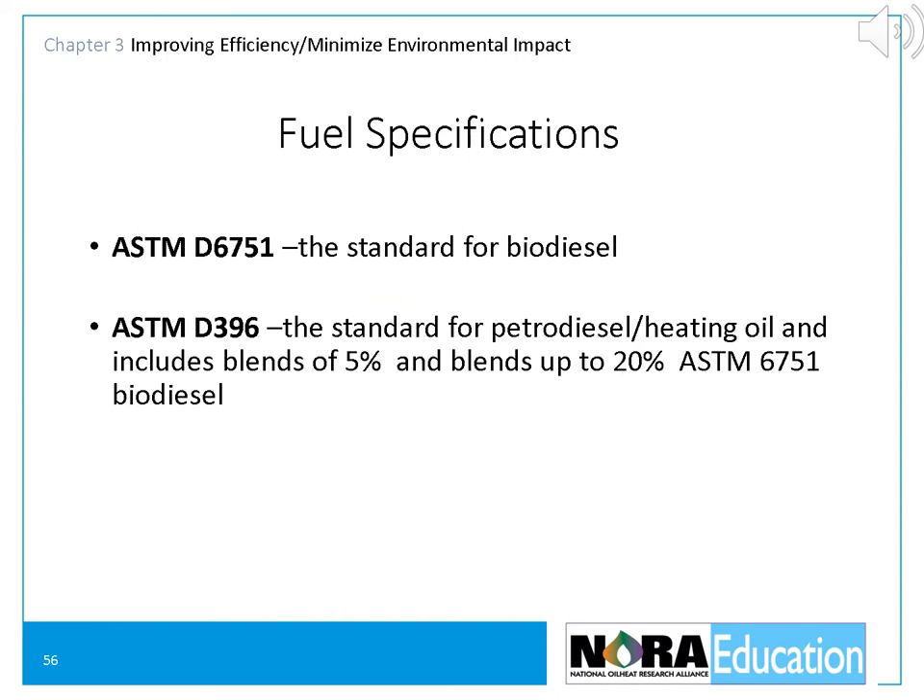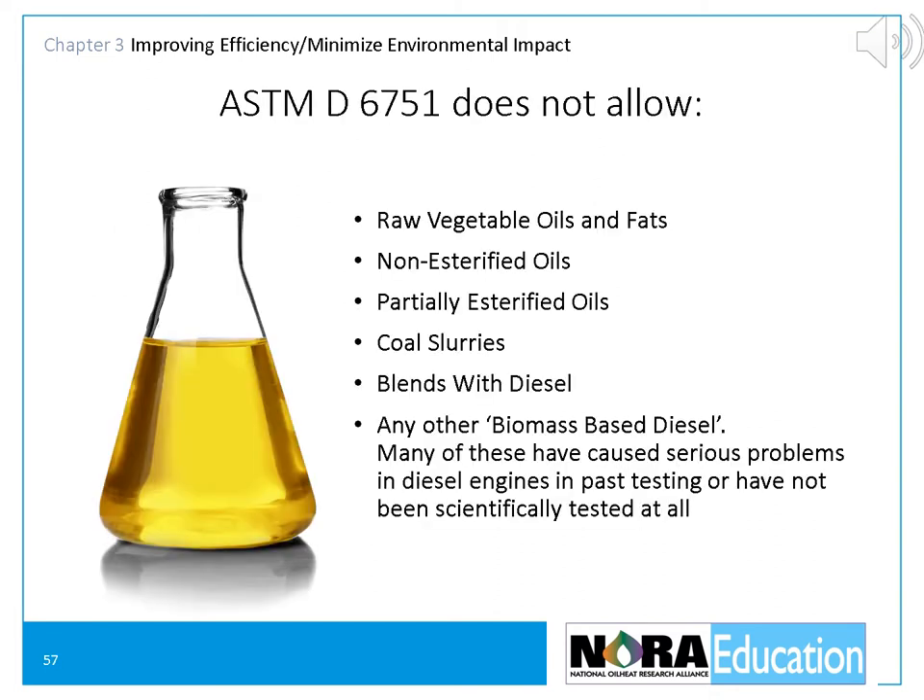Biodiesel is manufactured to demanding standards specified by the American Society for Testing Materials, or ASTM. ASTM D6751 describes biodiesel, and ASTM D396 describes a heating oil blend from 5% biodiesel up to 20% biodiesel and petroleum regular number 2 oil. ASTM D6751 standards do not allow the use of raw vegetable oils and fats as biodiesel — they don't allow non-esterified oils, partially esterified oils, coal slurries, or blends with diesel, or any other biomass-based diesel. Many of these have caused serious problems in diesel engines in past testing or have not been scientifically tested at all, and therefore are not allowed to be blended with heating oil and named bioheat.